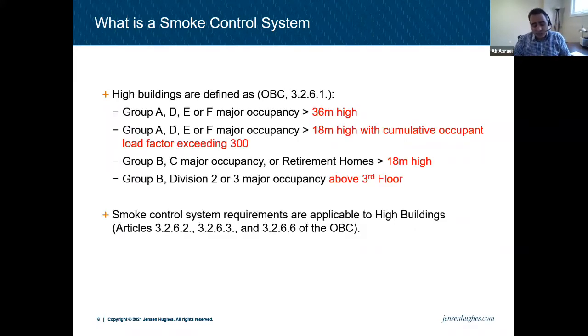And in the OBC, there are requirements for that, and it's for high buildings. There are two areas in the OBC that cover the smoke control system. One is 3.2.6 in the Ontario Building Code that talks about high buildings. So high buildings are the types of buildings that you see on the screen. If you're group A, D, E, or F major occupancy over 36 meters high, that's a high building. Or the same major occupancy over 18 meters high, with a cumulative occupant load factor exceeding 300. There's a bit of calculation involved there. If you're over 18 meters, it potentially could be a high building.